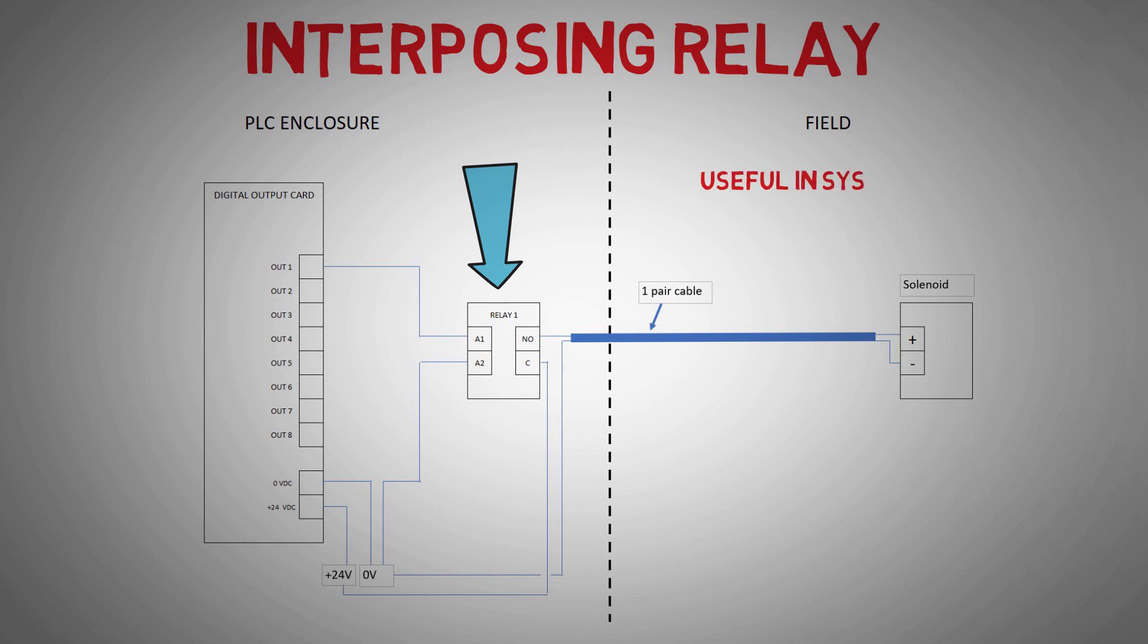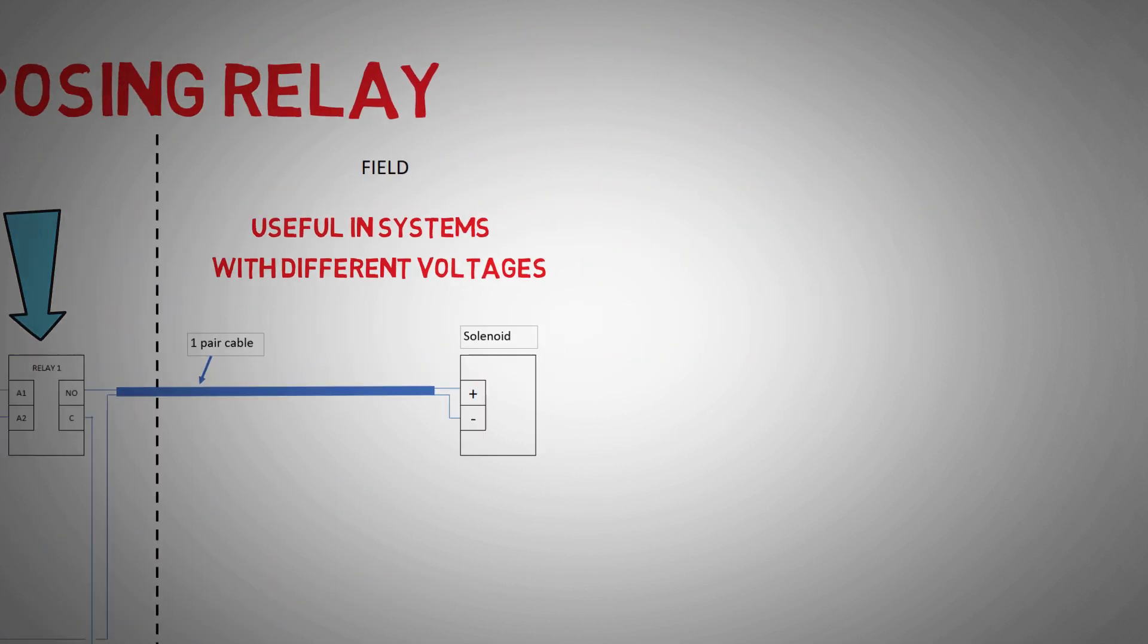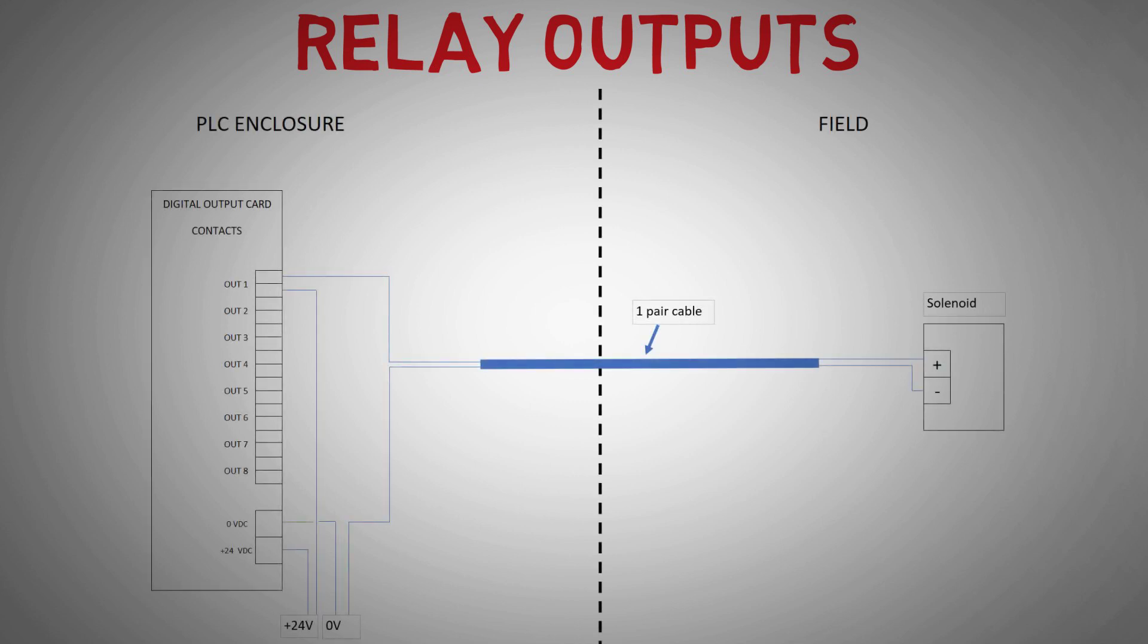This is useful if field devices require different voltages than the PLC. In our next card configuration, we have a relay contact card. Instead of providing power directly from the channel output, when activated this channel closes the contacts, allowing us to supply another component—in this case, the field solenoid via the 24-volt supply.